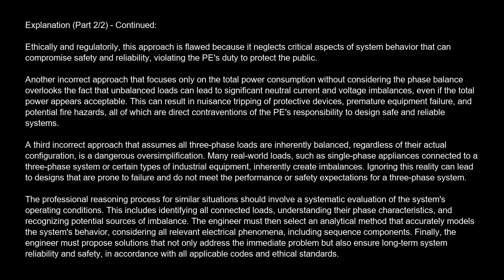Another incorrect approach that focuses only on total power consumption without considering phase balance overlooks the fact that unbalanced loads can lead to significant neutral current and voltage imbalances, even if the total power appears acceptable. This can result in nuisance tripping of protective devices, premature equipment failure, and potential fire hazards, all of which are direct contraventions of the PE's responsibility to design safe and reliable systems.